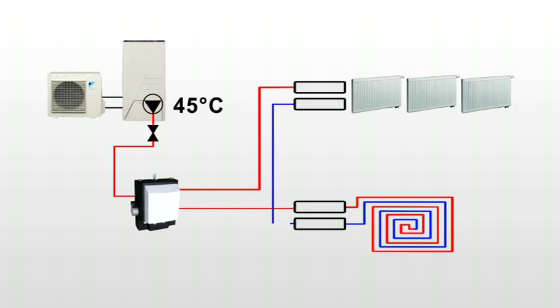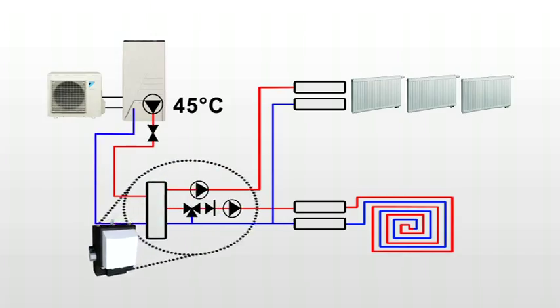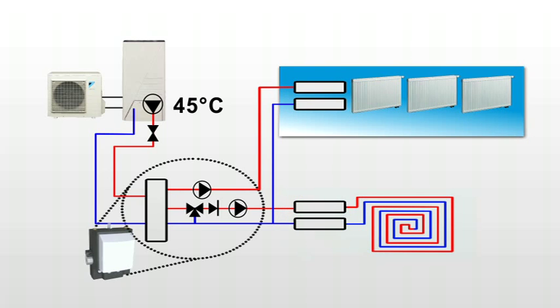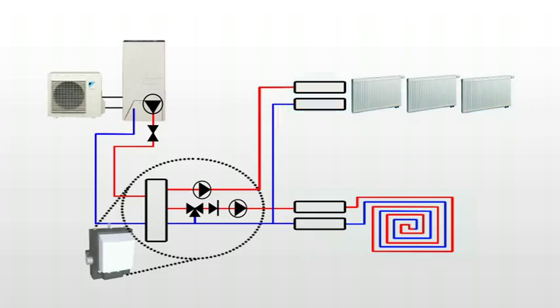And there's more. Combining underfloor heating with radiators divides your house into two zones: an underfloor heating zone at 35 degrees Celsius and a radiator zone at 45 degrees Celsius. To reduce the high water temperature to the 35 degrees Celsius at which the floor heating system is designed, a two-zone kit is necessary. And if this kit, including two pumps, can be omitted, it makes your installation even more energy efficient and also decreases the cost of your installation.